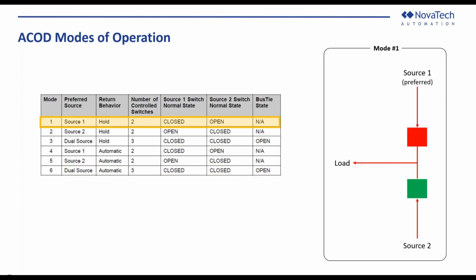So let's see, starting in mode 1, source 1 is your preferred source, source 2 is the alternate. In the graphic here, the switch for source 1 is closed, depicted as red, and source 2 is open, green. These are going to be the normal positions when operating in this mode. If potential is lost on source 1, that switch is going to be opened, and then the switch on source 2 will be closed. And now ACOD has transferred to its alternate source. This mode is called hold, because once ACOD switches to the alternate source, it will not transfer back to its preferred source, even if the potential returns there.